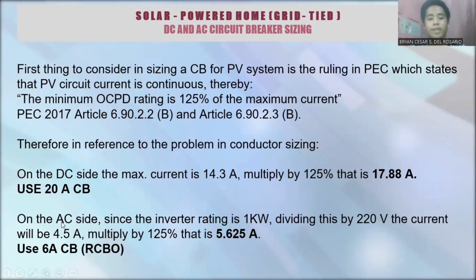So dito naman sa AC side, since the inverter rating is 1 kilowatt hour, yung na-compute natin kanina, dividing this by 220 volts, kasi yun yung standard na volts na gamit natin dito sa Pilipinas, the current will be 4.5 ampere. So yung 4.5 ampere na yan, multiply ulit natin sa 125%, lalabas is 5.625 ampere. Since wala ulit yung ganyan, gagamit tayo ng 6 ampere circuit breaker or RCBO.